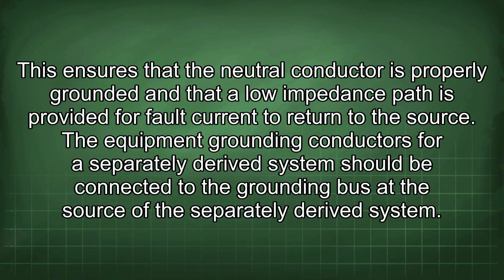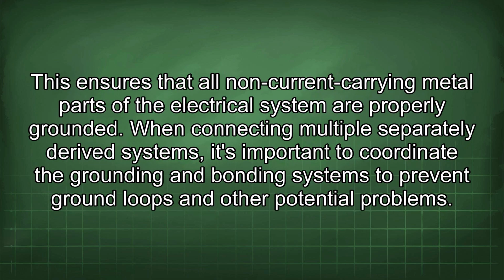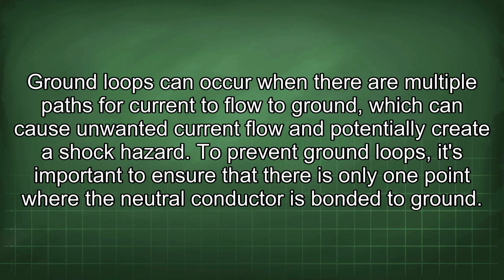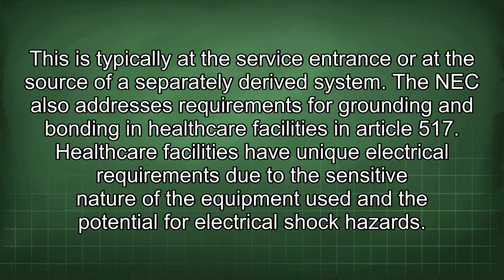The equipment grounding conductors for a separately derived system should be connected to the grounding bus at the source of the separately derived system. This ensures that all non-current carrying metal parts of the electrical system are properly grounded. When connecting multiple separately derived systems, it's important to coordinate the grounding and bonding systems to prevent ground loops and other potential problems. Ground loops can occur when there are multiple paths for current to flow to ground, which can cause unwanted current flow and potentially create a shock hazard. To prevent ground loops, it's important to ensure that there is only one point where the neutral conductor is bonded to ground. This is typically at the service entrance or at the source of a separately derived system.